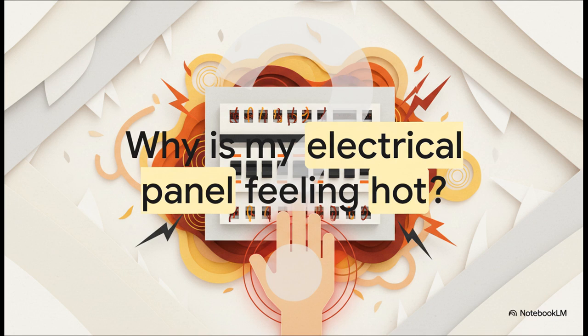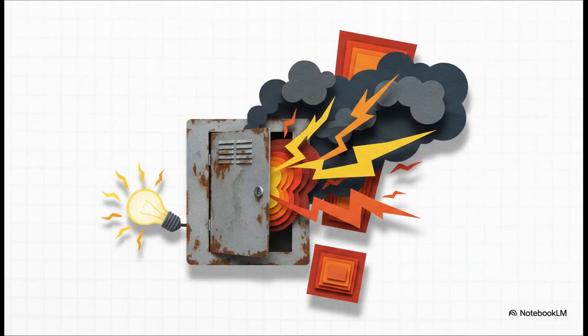It could mean there is a sustained high current draw, a loose internal connection that's generating heat through electrical resistance, or maybe even failing breakers. Make no mistake, panel heat is one of the clearest, earliest indicators of an impending failure. Let's run through the full list of these warning signs.